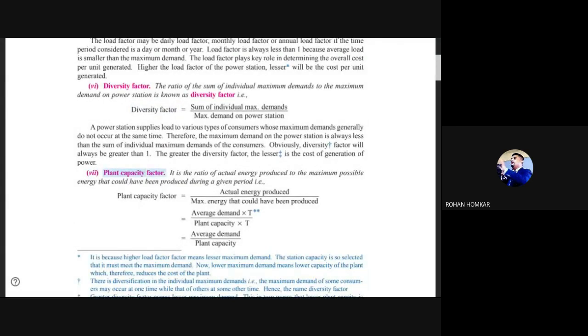Plant capacity factor is the ratio of actual energy produced to the maximum possible energy that could have been produced during a given period. For example, a 500 MW plant run for 24 hours could produce 500 MW × 24 = 12,000 MWh — that is the capacity. But what matters is how much electricity is actually consumed; based on average demand, the plant capacity factor is decided.